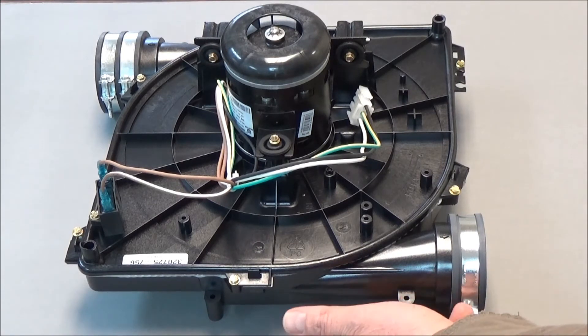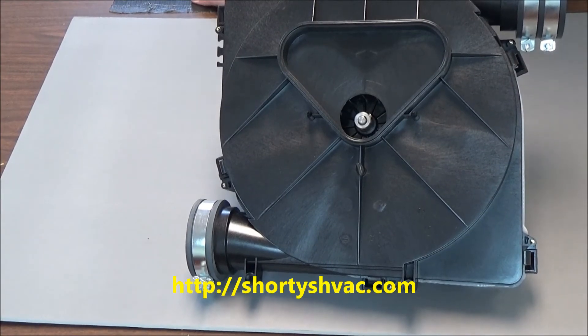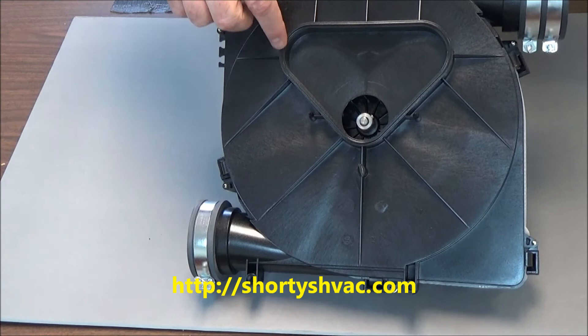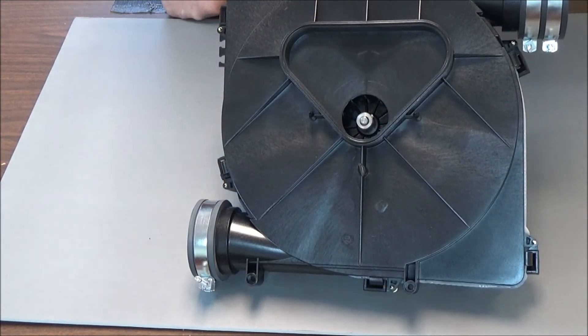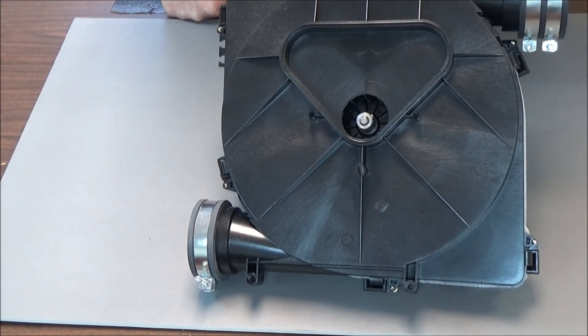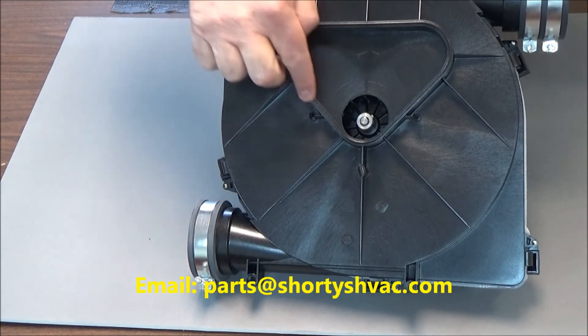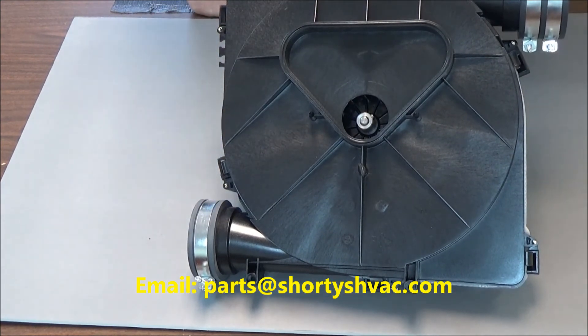There are spacers under here that you will reuse with your existing draft inducer. When you have the old draft inducer off, take a look at the collector box cover. There's a groove where this connects together right here — look at that, it's got a seal in it. If that seal is torn or not in too good of shape, you can remove it by spraying it with PAM and then put a real light bead of silicone around this before you put it back together. It's critical that that seals to keep flue gas from leaking out into your house.